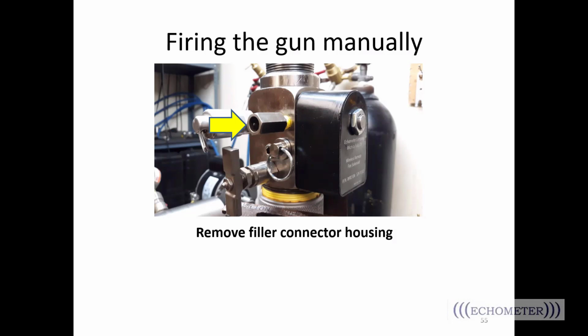Yes, another thing that they might try, it takes longer, is pushing that other filler connector, the quick connector other than the one used for permanent connections. This one, we have the cap on it right now. We can't see the connector itself, but just by pushing that, it will take longer depending on how much pressure you have in the chamber, but you can also decrease or bleed the pressure in the chamber by pushing that connector.